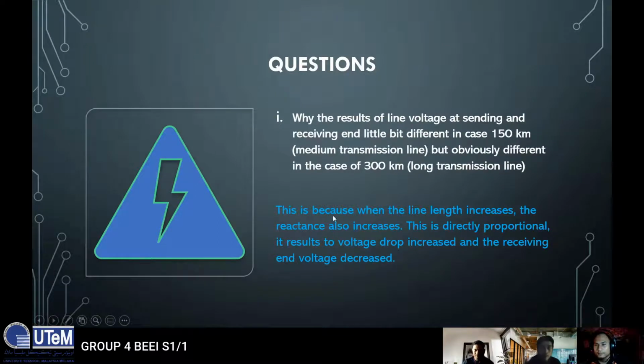For the question: for the no load, why is the result of line voltage at sending and receiving end a little bit different in the case of a 150 km medium transmission line, but obviously different in the case of a 300 km long transmission line? The answer is because when the line length increases, the reactance also increases. It is directly proportional. It results in voltage drop increasing and the receiving end voltage decreasing. So that's why.